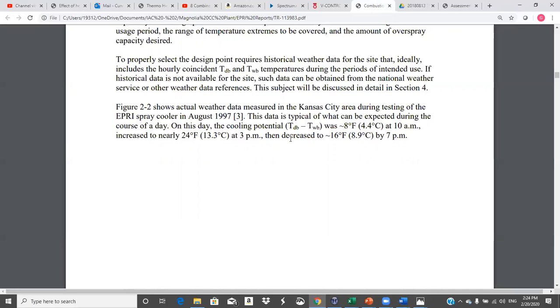So they're saying it was about 8 degrees at 10 a.m., increased to nearly 24 degrees at 3 p.m., and then decreased to 16 degrees by 7 p.m. So, you know, that's the best you could do. And so for this media that TVA was using, they were using a Munters product called CELdek. And CELdek advertised 88% efficient, which means you could achieve 88% of the wet bulb depression.